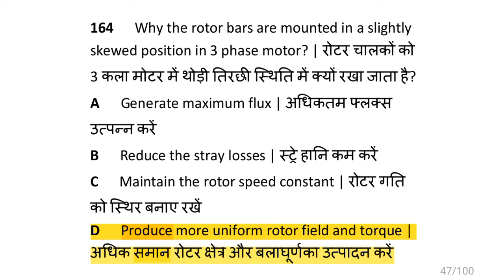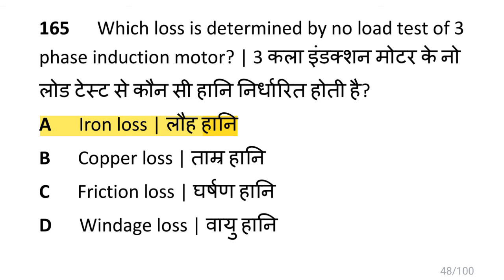Rotor bars are mounted in a slightly skewed position in a three phase motor to produce a more uniform rotor field and torque. The loss determined by the no load test of a three phase induction motor is iron loss.